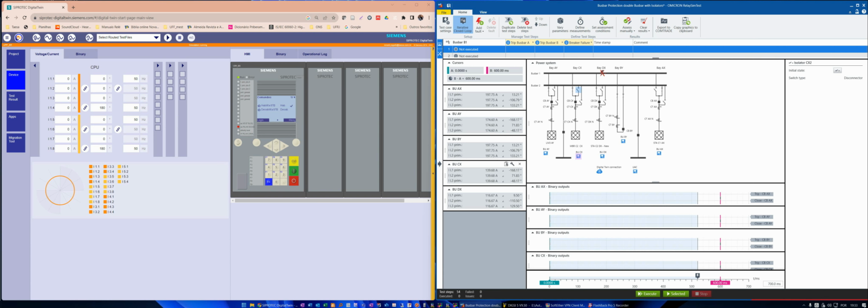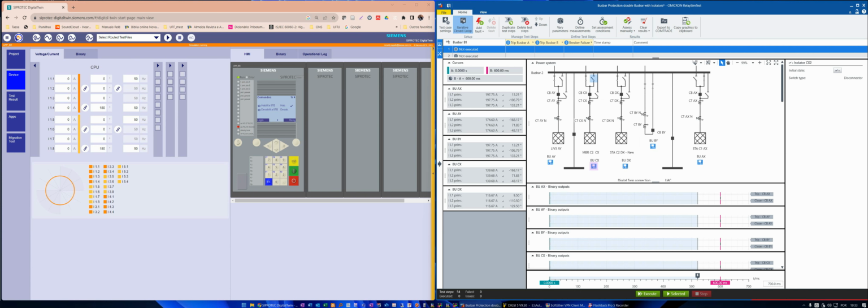This example of bus bar protection that we are testing is, for example, if we construct a new bay of this kind, it will be this bay, DX. And for example, if you want to know whether the configuration in my bus bar protection is correct, and all the settings and the logic are correct, we can do a simulation with just two software tools and validate the new settings and the new logic.